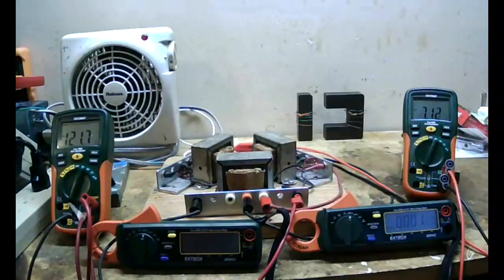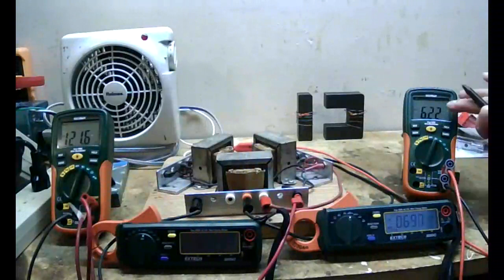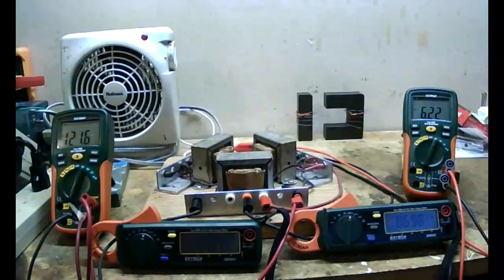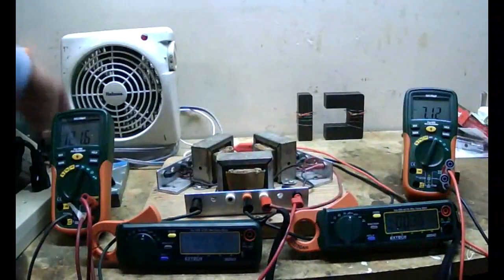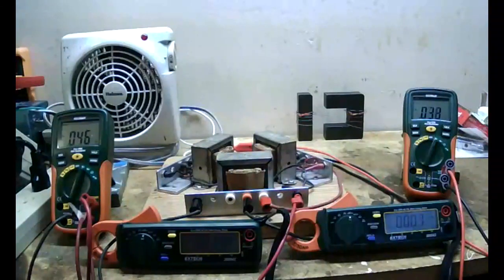We can't trust that. I'm going to turn on the load. I'm not going to leave it on very long because it's hard on that motor to be energized when it's not turning. So, with load, we have primary voltage 122, secondary voltage 6.2. Interesting, the voltage has dropped significantly on the secondary when I turned on the load. Secondary current is no longer 0. It's reading 698, 697, so we will call that 700 milliamps or 0.7 amps. That's all I need. I'm going to come back to the primary reading, but for now we're going to just use the secondary values to calculate primary values.